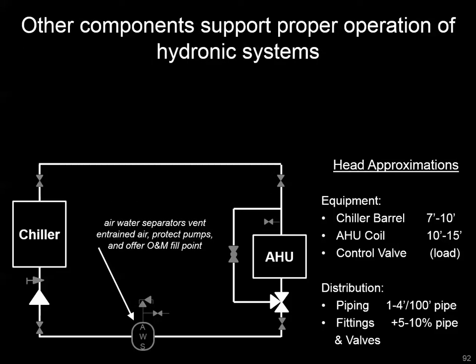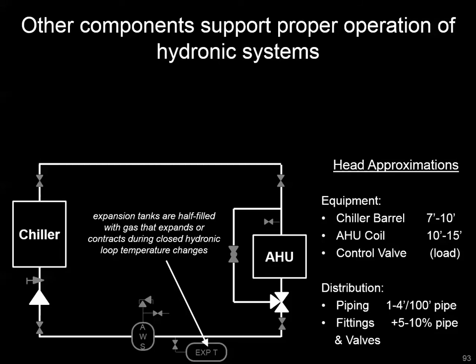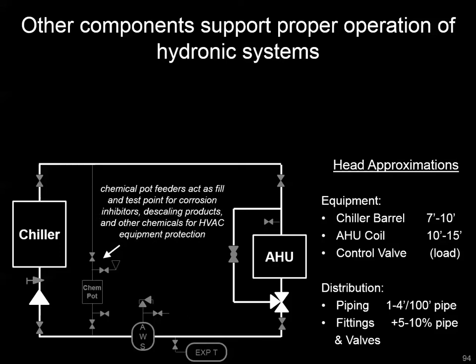There are other components in the hydronic system. An air-water separator helps remove entrained air, protects pumps and other equipment, and acts as a water makeup point. Expansion tanks accommodate density changes in the water as temperature changes — an air bladder in the tank allows for expansion and contraction of the system. You'll typically have in the plant a chemical pot feeder, which is a point to test and add chemicals like corrosion inhibitors and scale treatments. That's usually a very thin bypass that should be valved off when not in use, but opened up when circulating chemicals through the system.